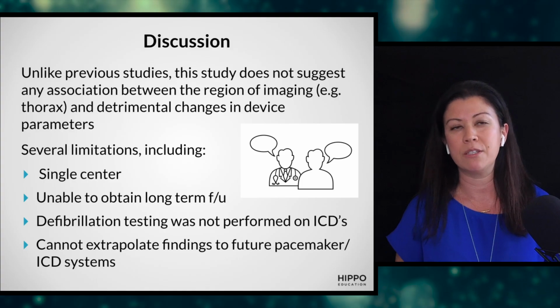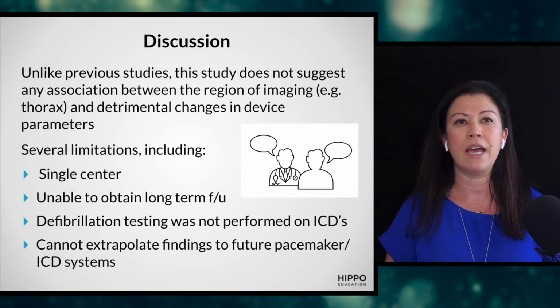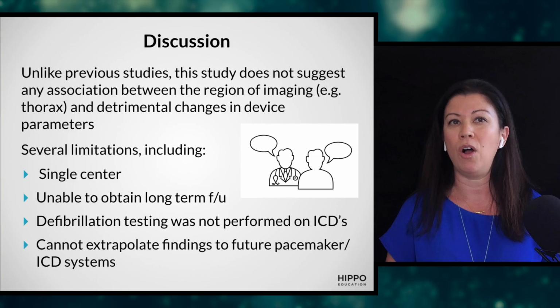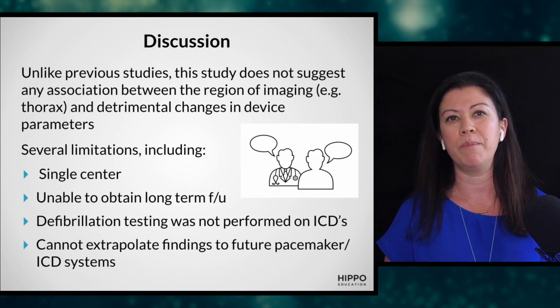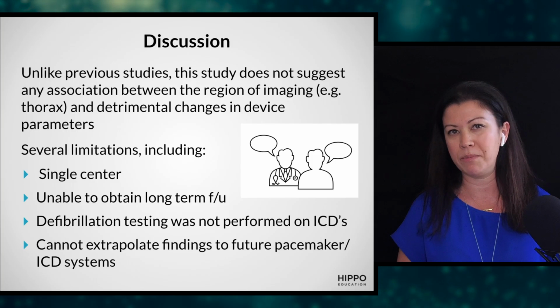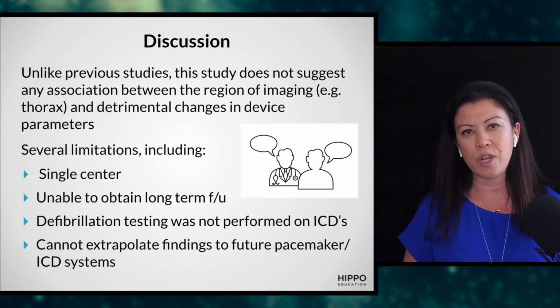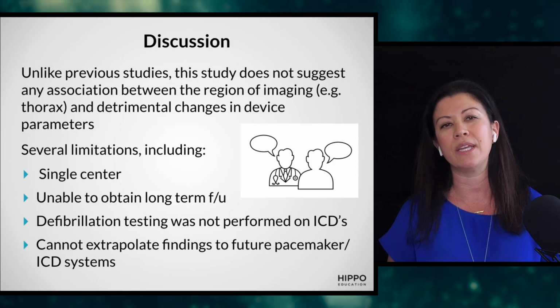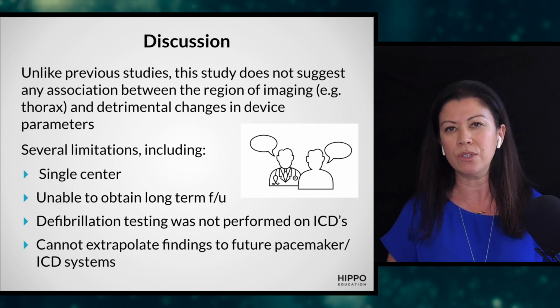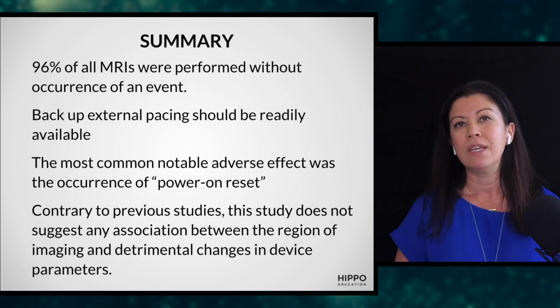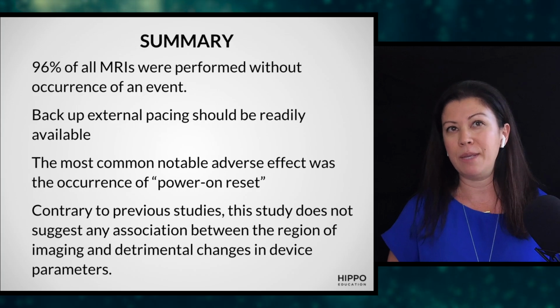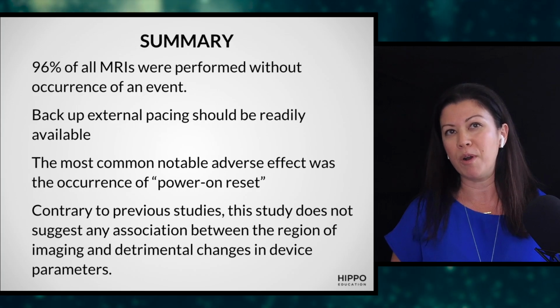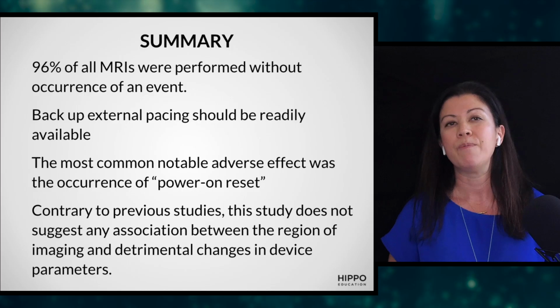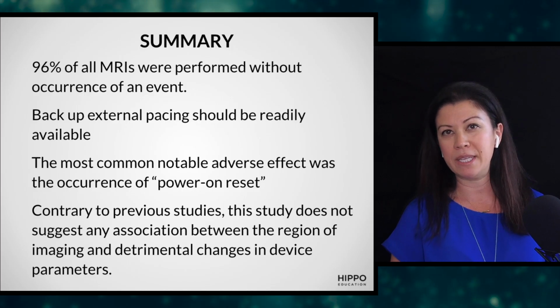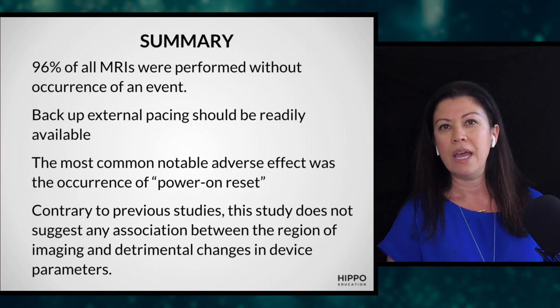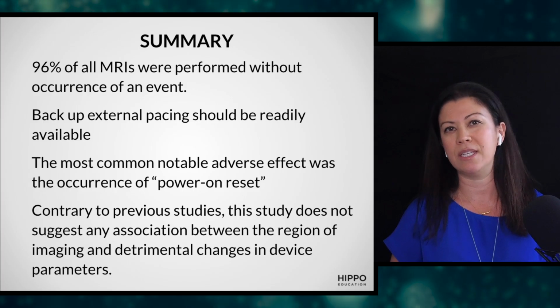Now, there were a few limitations. This was a single center only. It was unable to have long-term follow-up for all the patients, right? Only 60% of them had long-term follow-up. Defibrillation testing was not performed on ICDs afterwards. And so you can't extrapolate findings to future pacemakers and ICD systems. So those are the limitations, but it certainly does pose a good question. And in their summary, 96% of all MRIs were performed without an occurrence of an event, so fairly safe. Now remember, they had backup external pacing readily available. That was important. And the most notable adverse effect was this power on reset.